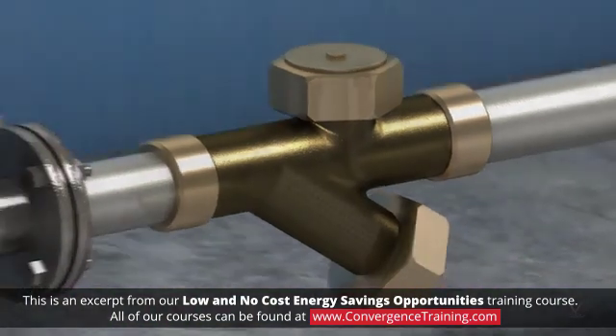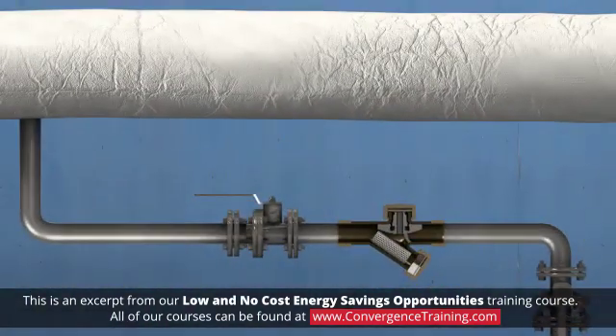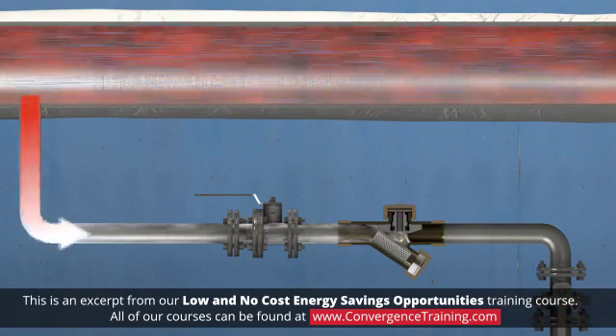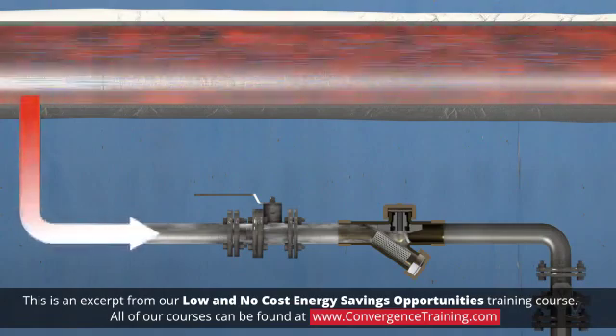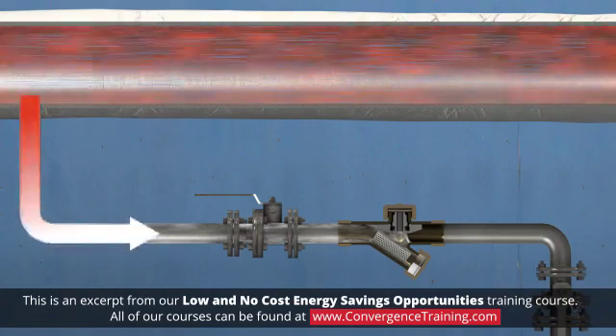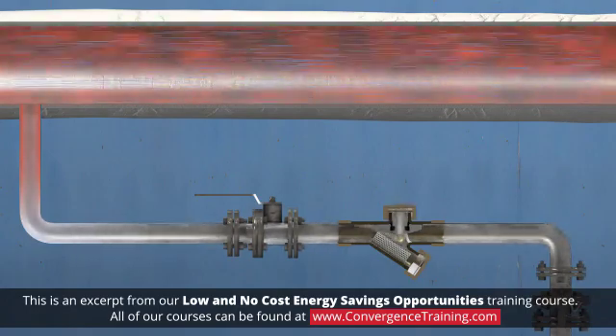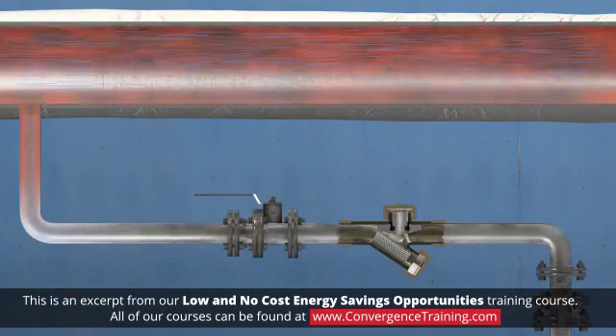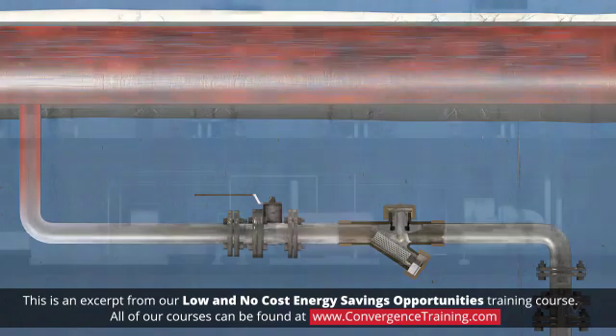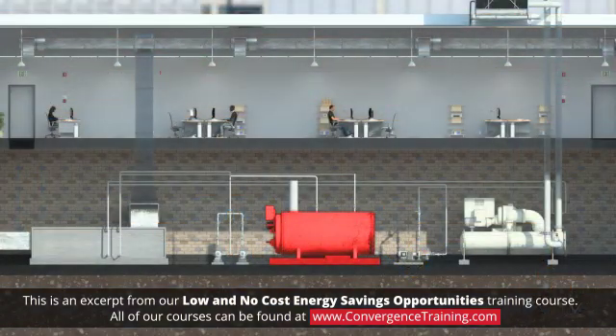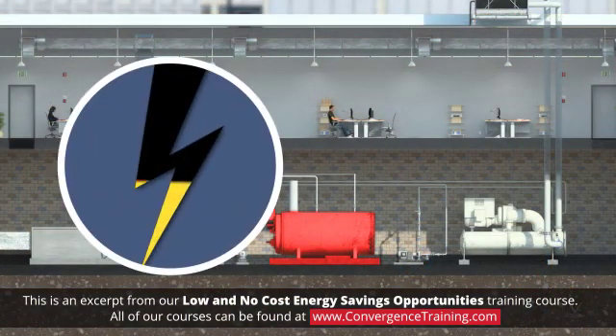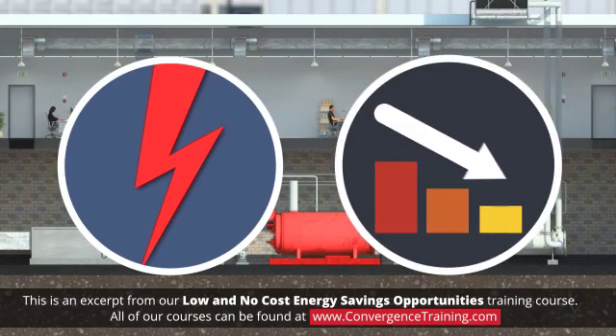Steam traps represent another potential silent energy loss. Steam traps separate steam from hot condensate in condensate return systems. If they fail, they can allow steam to leak through them and eventually escape the system. Although the heating system will appear to operate normally, energy consumption will increase and efficiency will drop.